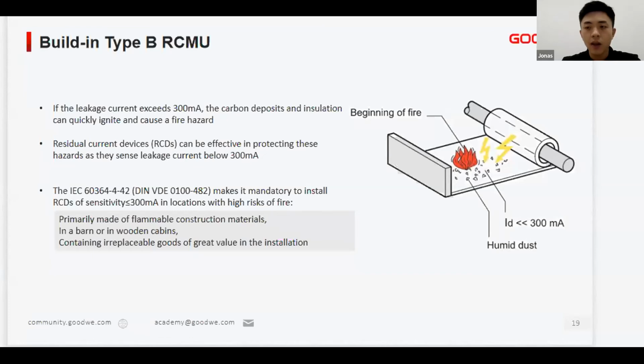Another cause of fire is the residual current. Sometimes fires caused by ground fault currents should also be prevented at a very early stage, and it's very critical in an agricultural environment. In a dusty and humid environment, the insulation failure between the line conductor and the ground may cause a low intensity arc fault, but high enough to cause a fire. Some tests have shown that even a fault current of 300 milliamperes can induce a real risk of fire. However, this type of fault current is too low to be detected by overcurrent protection.